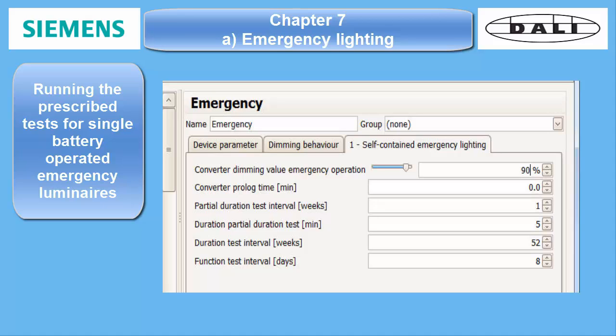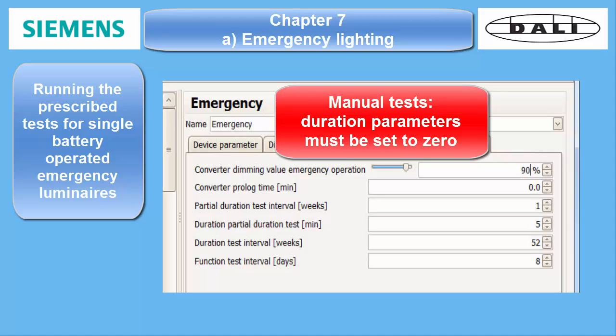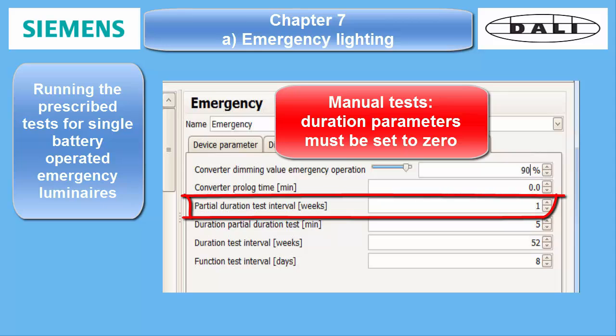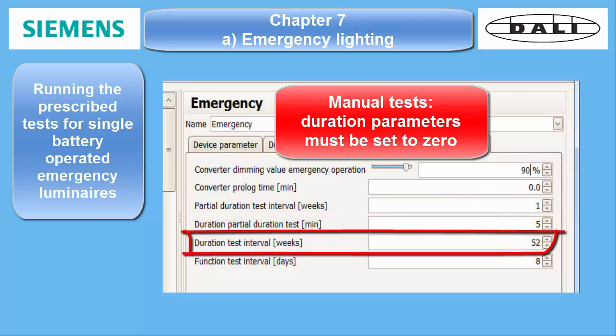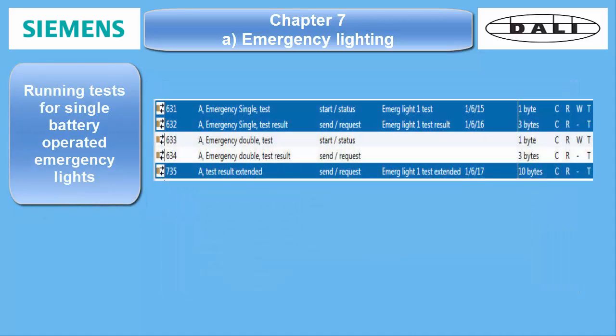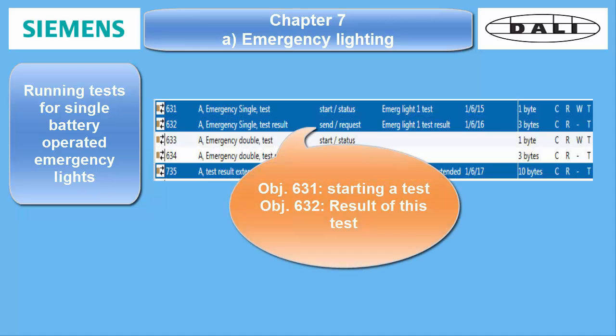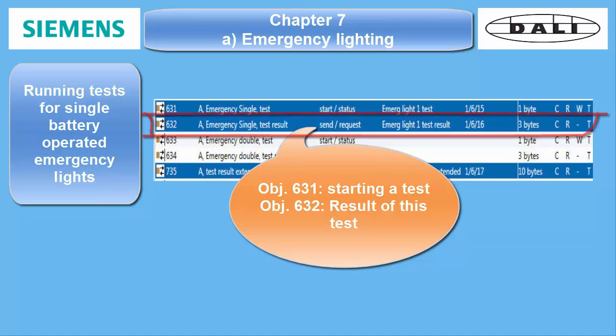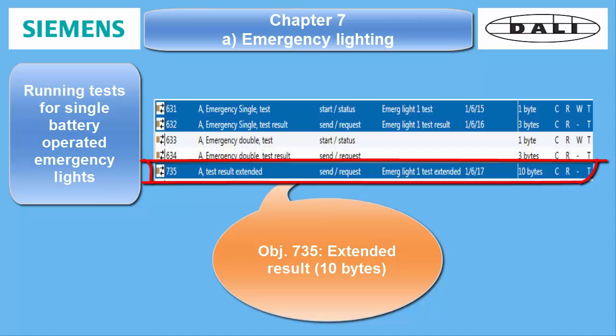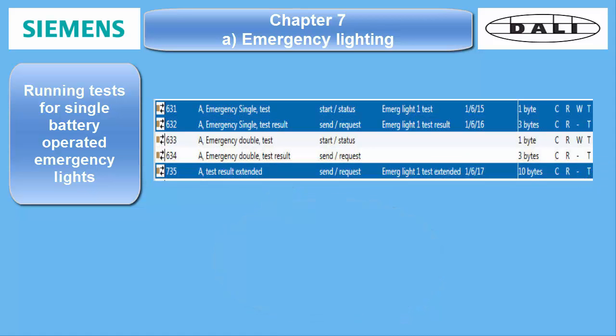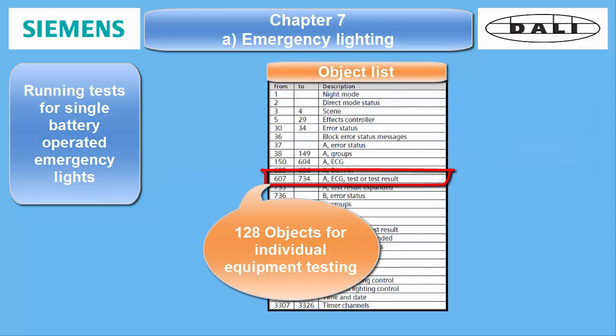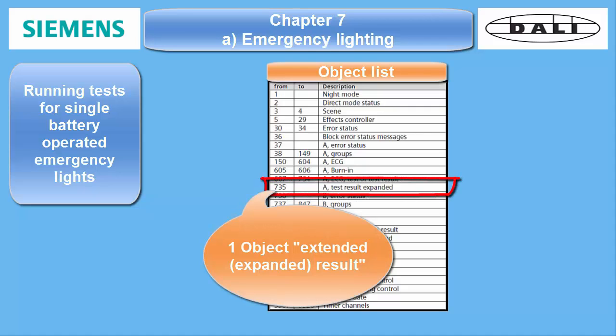However, if the facility management wants to run these tests manually, the automatic function can be switched off in the parameter settings — the duration test parameters must both be set to zero. For manual test triggering, two communication objects are available: the individual simple test control object (number 631, 1 byte) with its result object (number 632, 3 bytes), and the extended test object 735 for channel A, which comprises 10 bytes. While the simple test objects come along with each emergency ECG, the extended object is unique for each channel, meaning the ballast number is encoded in the extended test result.